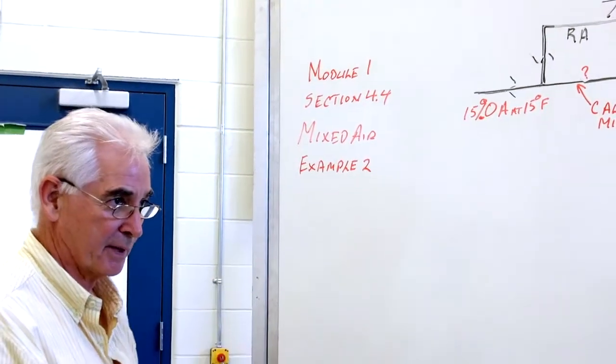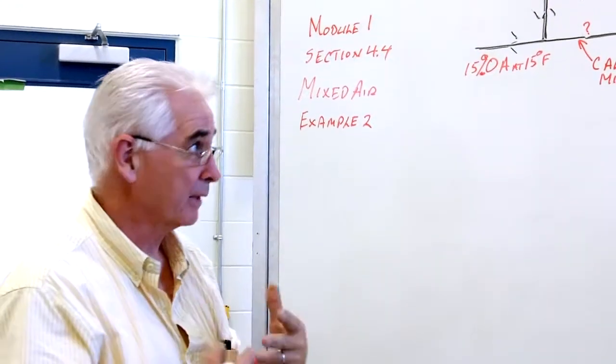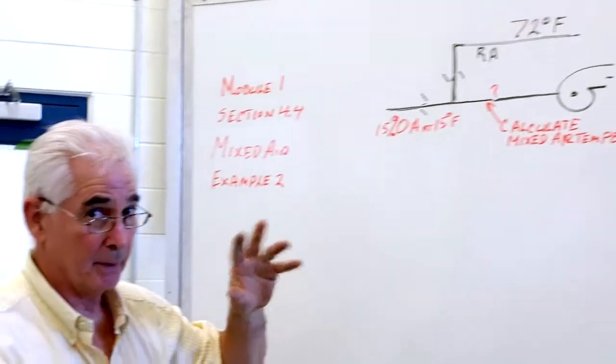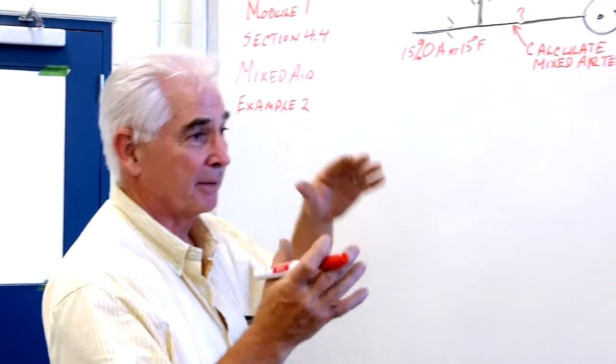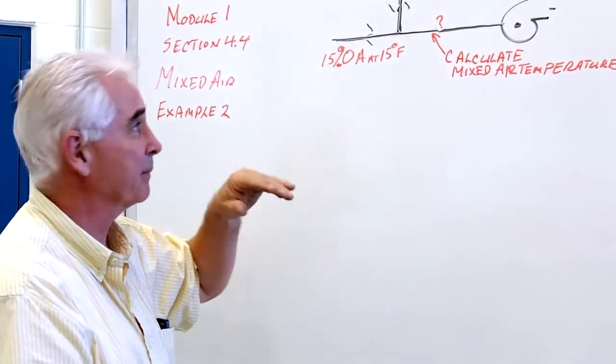We frequently, as TAB technicians, have to calculate what should the mixed air temperature be, and that's to help the building automation guy determine if he has the right setting for the dampers.